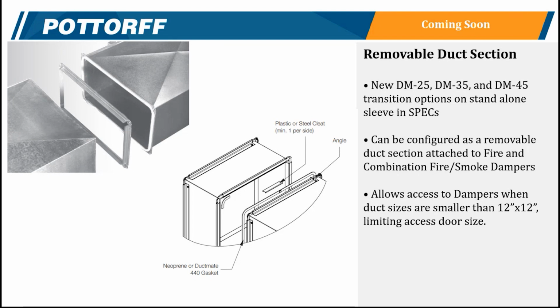We also have an installation instruction we're putting together to show you how to put this together with a UL approved breakaway connection for your fire or combination fire and smoke dampers. This will allow you to have a removable duct section when, say, on a 10 by 10 or some very small duct where you wouldn't be able to incorporate a 12 by 12 access door.